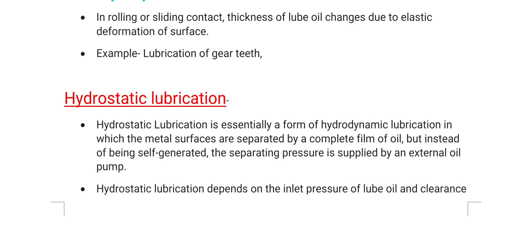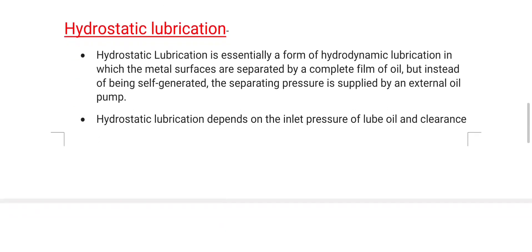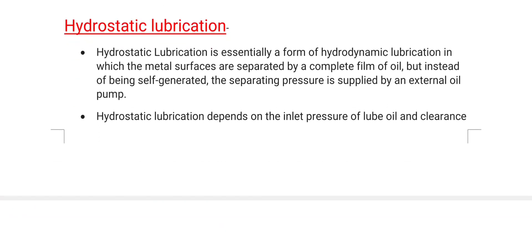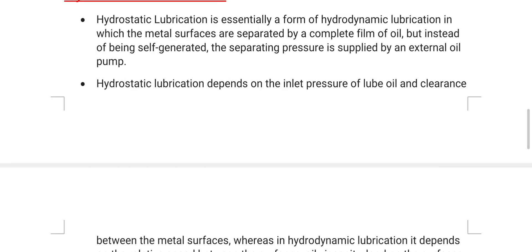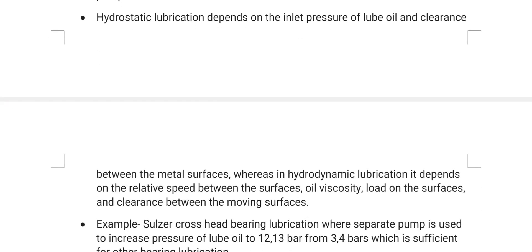The second type is hydrostatic lubrication. Hydrostatic lubrication is essentially a form of hydrodynamic lubrication in which the metal surfaces are separated by a complete film of oil, but instead of being self-generated, the separating pressure is applied by an external oil pump. Hydrostatic lubrication depends on the inlet pressure of lube oil and clearance between the metal surfaces, whereas hydrodynamic lubrication depends on relative speed, oil viscosity, load, and clearance between moving surfaces.